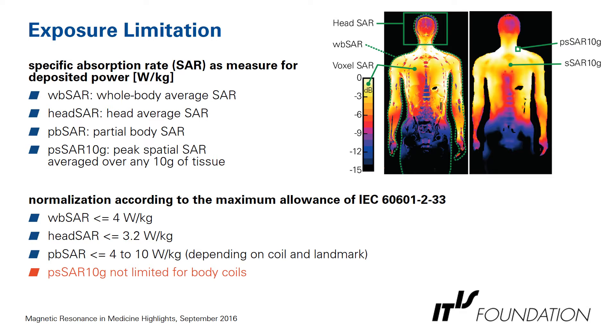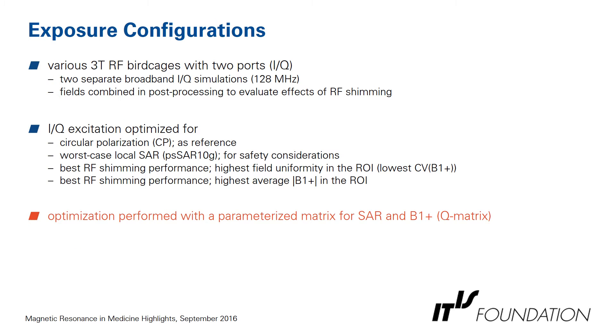The exposure limitation is done using SAR — specific absorption rate. Typically, whole body SAR, head SAR, and partial body SAR are used. The standard uses 10-gram averaged peak spatial SAR as a measure for local SAR. Normalization is always done according to the maximum allowance in product standard IEC 60601-2-33: whole body SAR less than 4 W/kg, head SAR less than 3.2 W/kg, and partial body SAR less than 10 W/kg. The peak spatial SAR 10g is actually not limited for body coils in the standard.